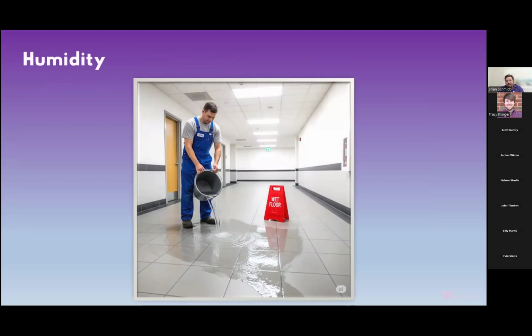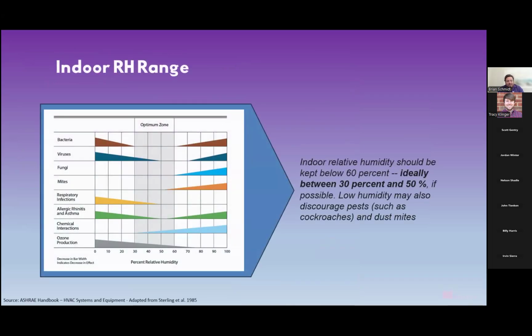So when we bring outside air into a building, again, our main concern is humidity. Don't need to really explain that to anyone on this call. Again, we're in the area of the country where that is definitely a top concern. So the indoor relative humidity range that we're looking for is really between about 30 and 60%. Anything below that, you can start promoting bacterial growth, viruses, respiratory infections, and anything above that, same exact thing. Now we're also talking about mold and bacteria. So we're really trying to keep it in that sweet spot between 30 and 60% relative.